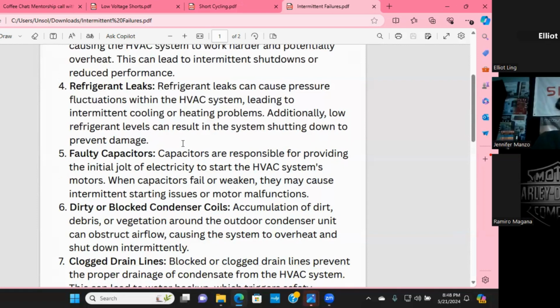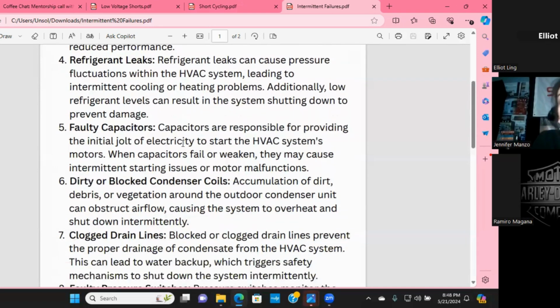Faulty capacitors. This is the big kahuna, you guys. When a capacitor is failing, it doesn't always fail outright. When a capacitor is failing, it will weaken its ability to run the fans correctly. It will still run the fan. And I get so many calls to tech support that are saying, my fans are running. It's not that. And I'm like, I don't care if your fans are running. I want to know how they're running. And the only way to do that is to test. If you're not testing, you're guessing. So always be checking, de-energizing and then testing your capacitors.